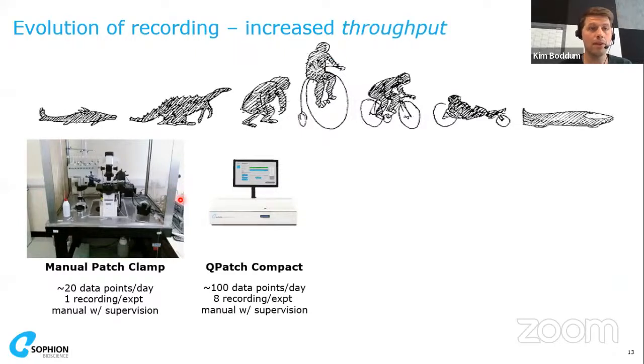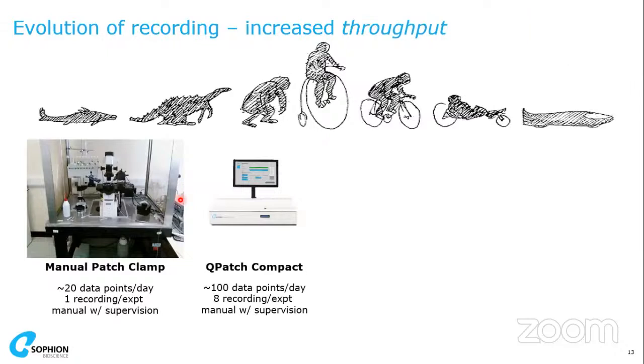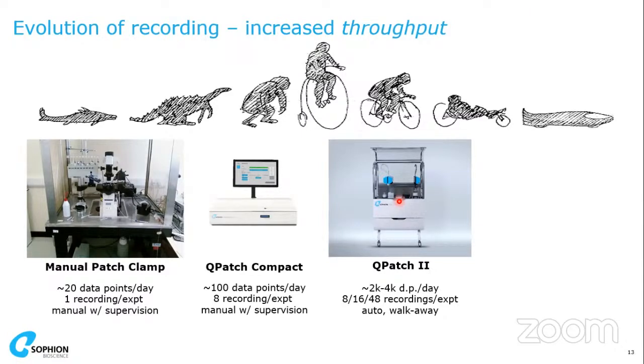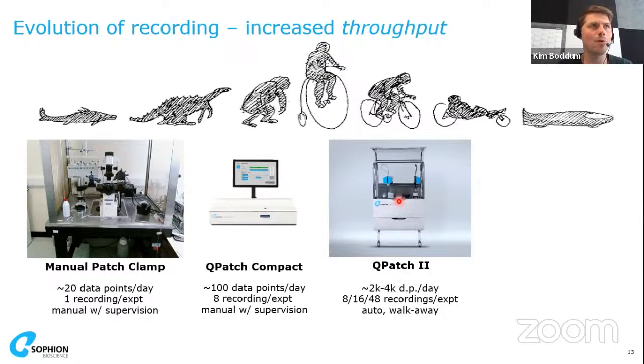And with grounding, you can avoid that noise. So by being in control of the system and all the noise, by grounding, we don't see that much noise. But in some of the systems, we also have a metal case surrounding the plate. The recording plate lays in here in the middle, so that is also to some extent shielding from noise. But mostly because we are producing all the components, we are capable of grounding all the components, and therefore we don't see that much noise.